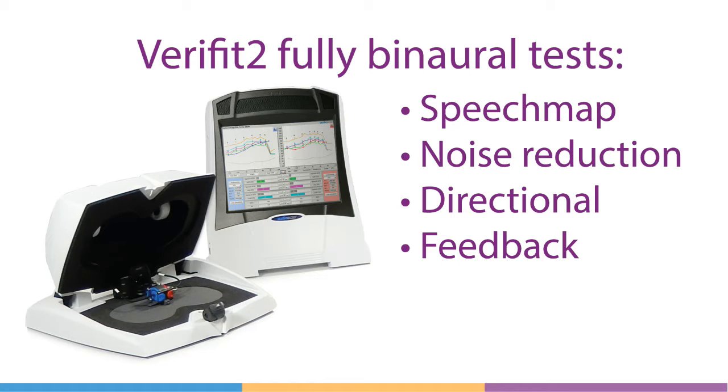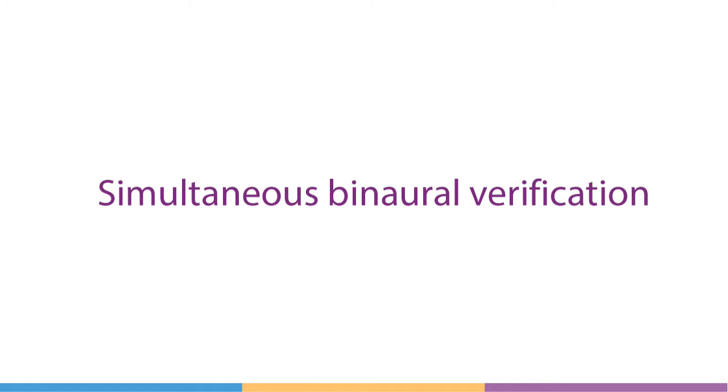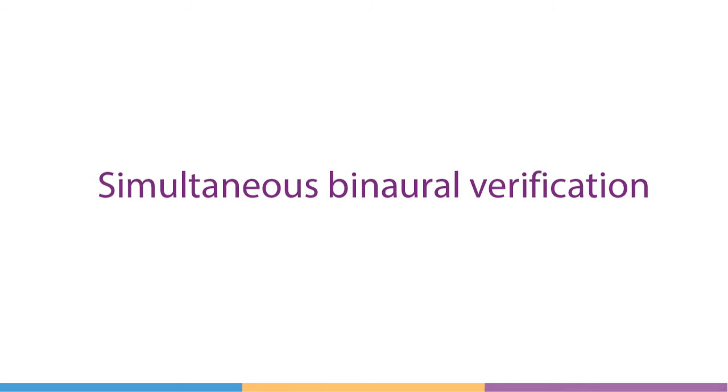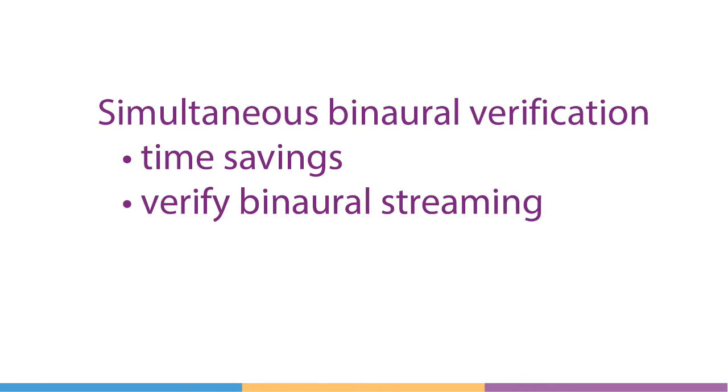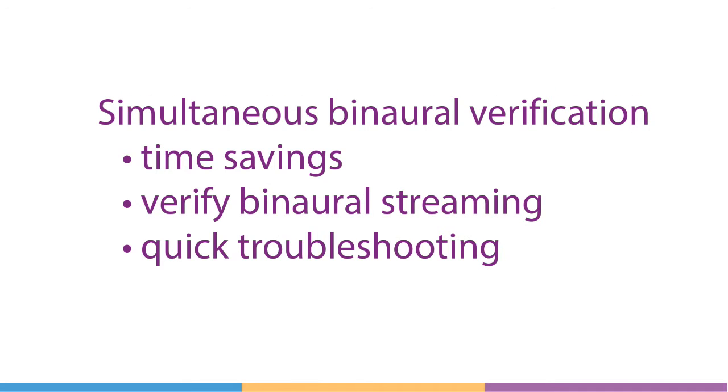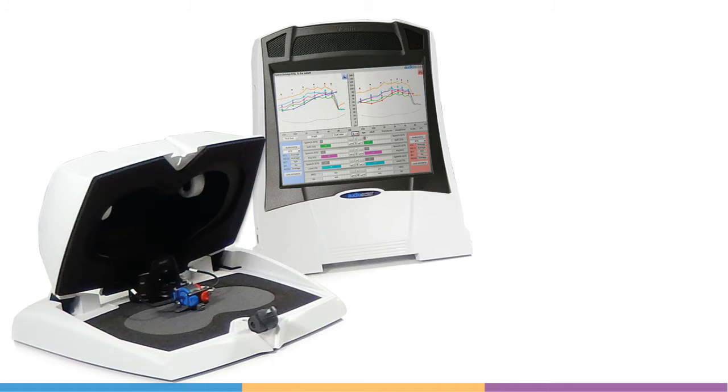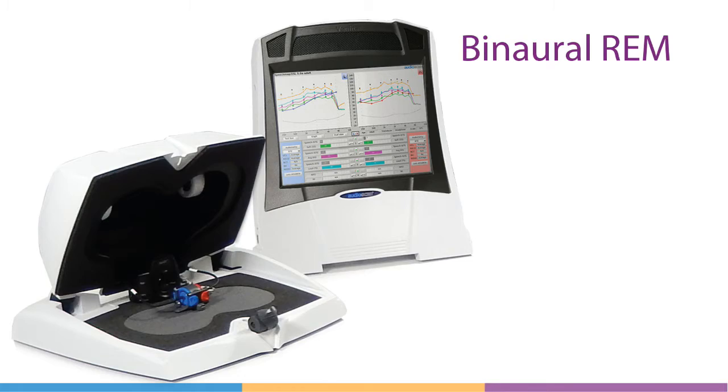Simultaneous binaural verification can provide several clinical advantages, including time savings, the ability to verify paired or streaming features, and quick identification of hearing instrument issues. The Verifit2 offers simultaneous binaural fitting to target for those using speech map on ear as well as in the test box.